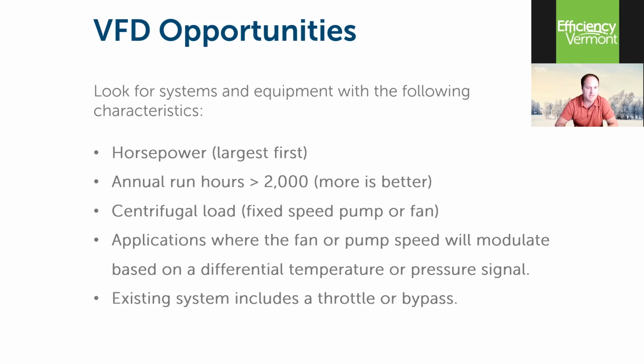Centrifugal loads, applications where fan or pump speed will modulate based on differential temperature or pressure. That's typically your two signals. Flow would be the other one. A drive can be controlled by multiple signals, but in most HVAC applications, it's usually temperature or pressure. And occasionally flow. Existing systems include throttle or bypass. Throttle and bypass is like a big red flag, but also a green flag in terms of opportunity. If we see throttling and bypass valves, that's usually a really good indication that there's a VFD opportunity there. All right, next slide.